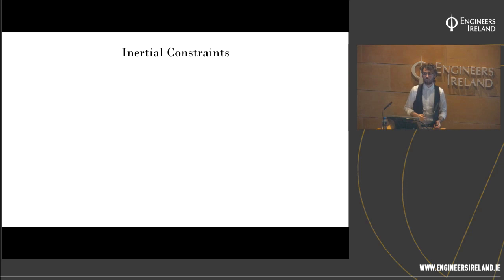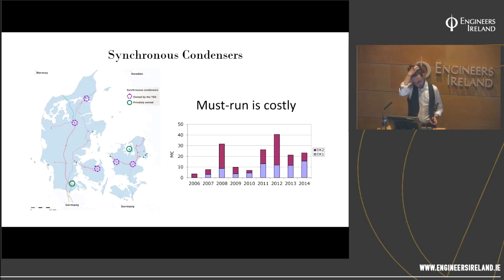What kind of power would a synchronous condenser consume? It's about 3% of rated capacity. Now that will change if it's idling. It depends how much on the reactive power production of the unit as well. But roughly 3% of the MVA. What is the rated capacity for the ones that are there? They're 270 MVA, so they're quite big. EnergiNet don't really have inertia problems because they're connected to the European grid, which is quite big.